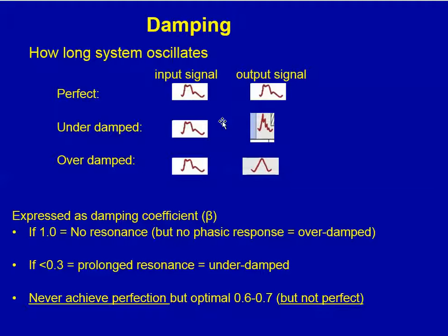The second problem with transducer systems is the phenomenon of damping. Damping refers to how long the system oscillates. In the perfectly damped system, the output signal would be identical to the input signal. In an under-damped system, the output signal has ringing with exaggerated spikes, and in the over-damped system, the arterial waveform is blunted.